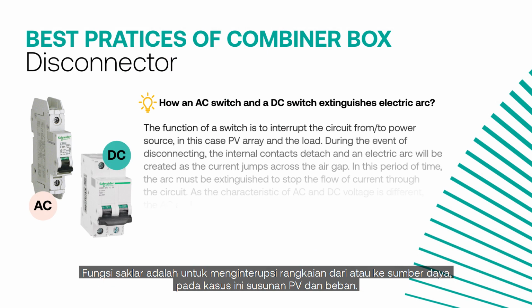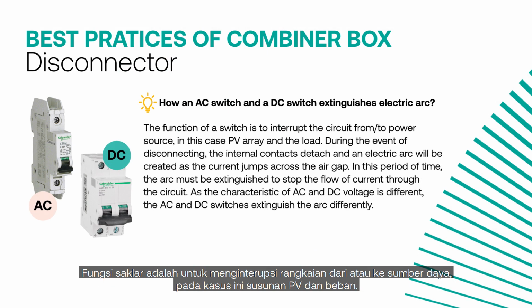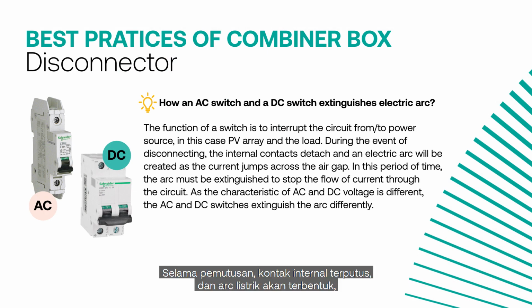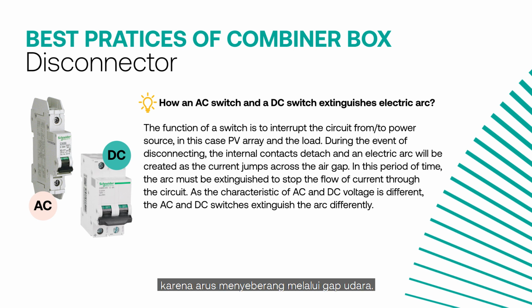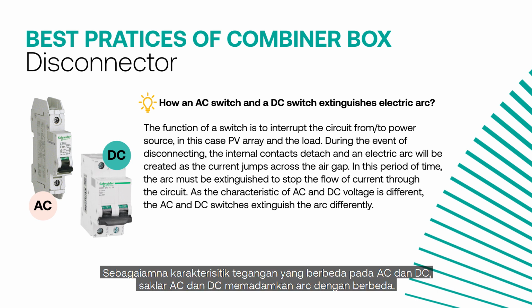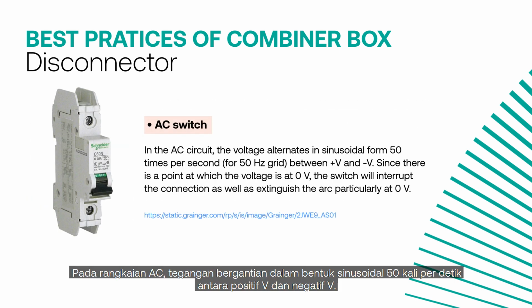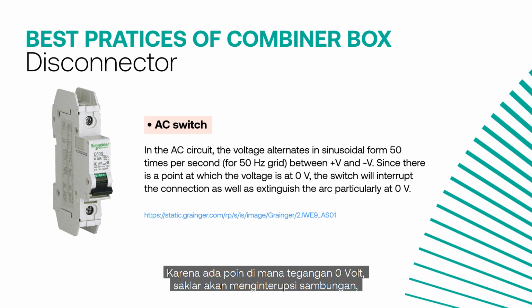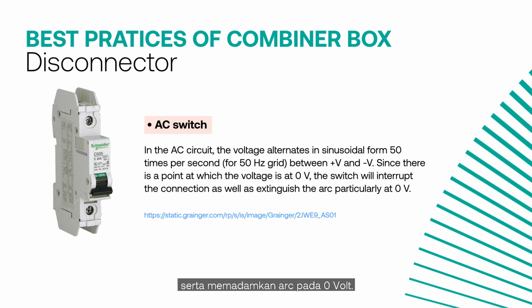The function of a switch is to interrupt the circuit from or to the power source, in this case the PV array, and the load. During disconnecting, the internal contact detaches and an electric arc is created as the current jumps across the air gap. In this period of time, the arc must be extinguished to stop the flow of current through the circuit. As the characteristics of AC and DC voltage are different, AC and DC switches extinguish the arc differently. In the AC circuit, the voltage alternates sinusoidally, 50 times per second, between positive volt and negative volt. Since there is a point at which the voltage is at 0 volt, the switch will interrupt the connection as well as extinguish the arc particularly at 0 volt.